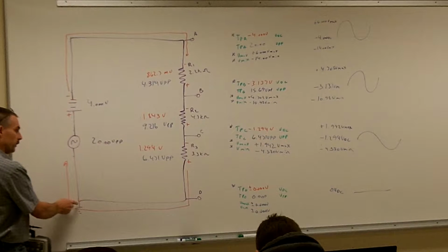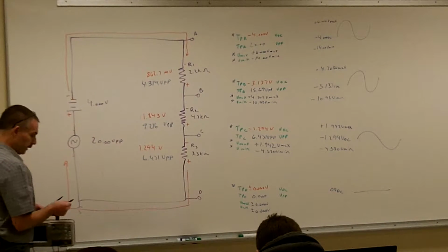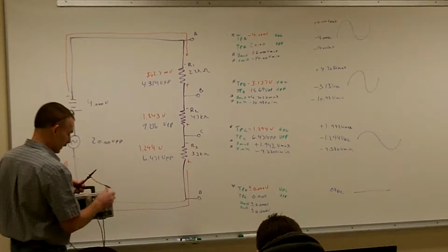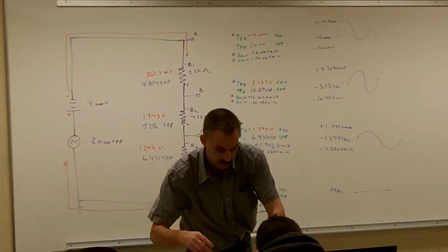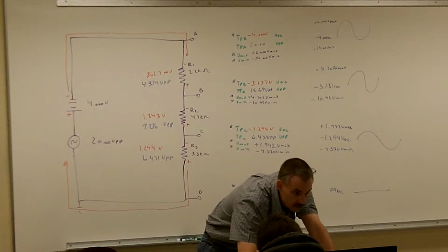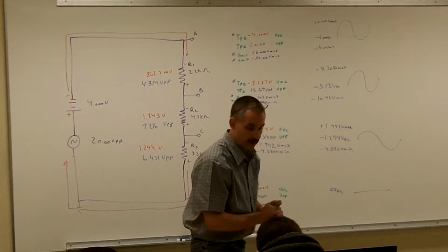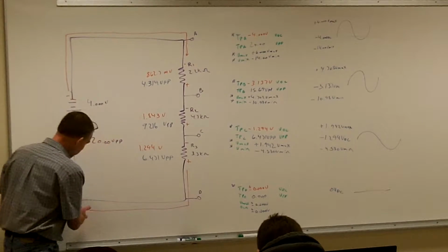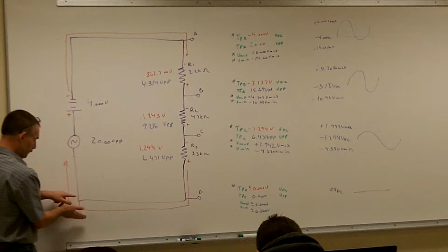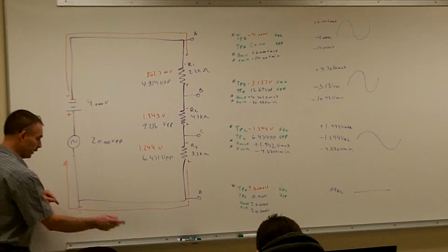Just like when we're doing test points, this ground clip can never move. And that's actually physically grounded to earth ground. It's not just a point of reference here. Yes, it's a point of reference, but when we hook up that ground clip from our probe and tie it right to here, we're physically tying this to our earth ground.